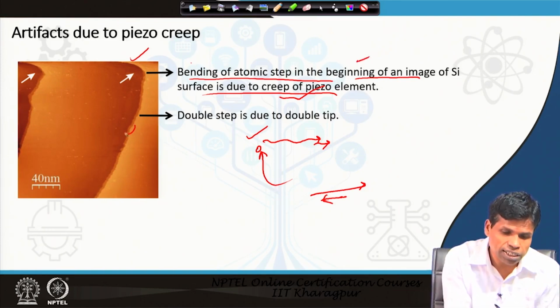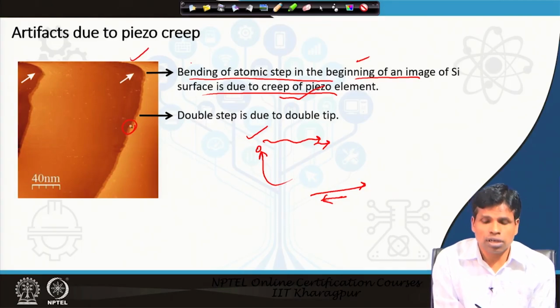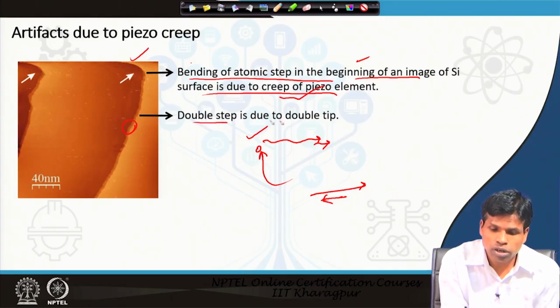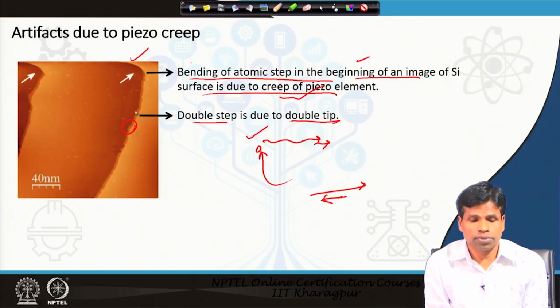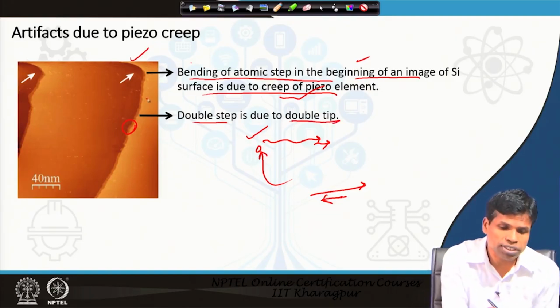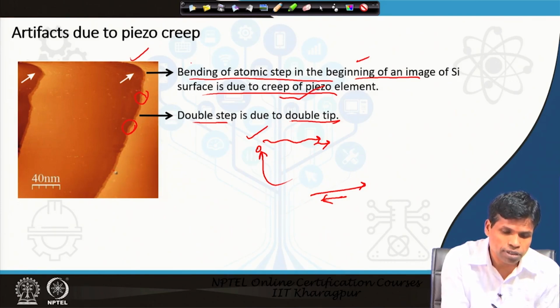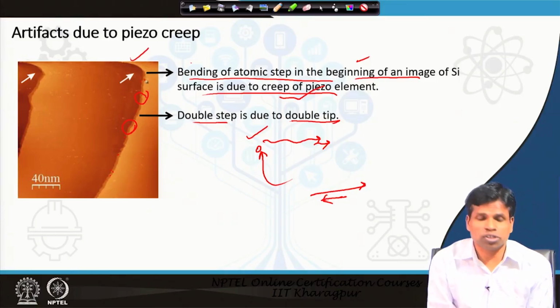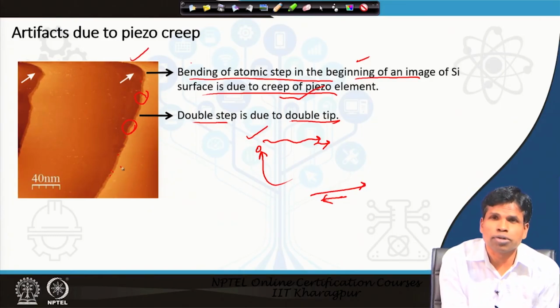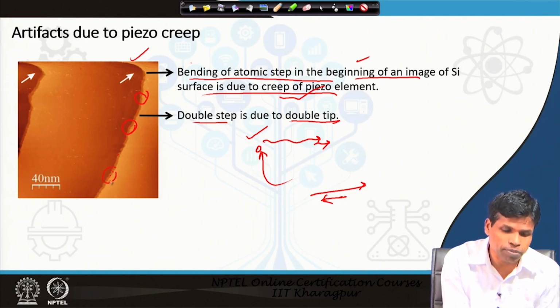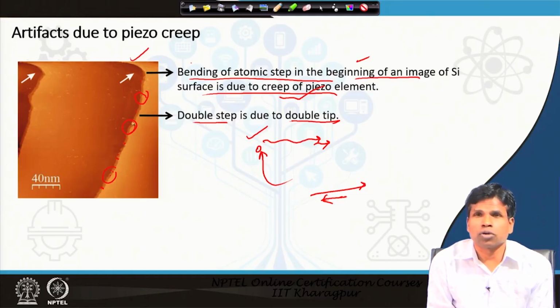Similarly, here you see this is actually a single step, but because of the double tip it is appearing as a double step. It is actually not a double step, but a single step. As you see, in every place the gap between these 2 points is always the same, fixed, indicating it is due to the tip effects, not actually the sample. If it were a double step in the sample, there is a rare chance that in every place the step gap would be almost equal.